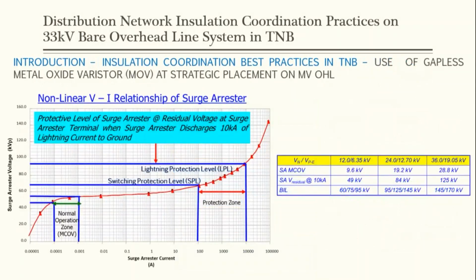Okay, so now we talk about the surge arresters. There is a non-linear voltage to current relationship of the surge arrestor. For example, during the normal operating zone, or the maximum continuous operating voltage, the surge arrestor will not conduct. But when it comes to the switching protection level or lightning protection level, it will start to conduct, and this will be the protection zone.